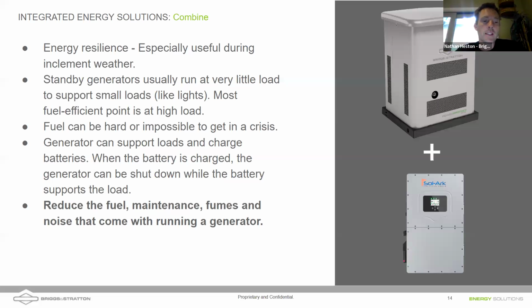One of the questions we often get is, cost is obviously a factor, right? So can I install an inverter with a battery system and then use a smaller portable generator? Yeah, absolutely. A couple considerations with portable generators is that they do have to be 240 volt in order to feed into that Sol-Ark. You're going to lose the capability of that automatic generator start. So you are going to have to be closely monitoring that great app that a lot of the inverter companies have, including Sol-Ark, to know when to start up that portable generator. So absolutely, you can.